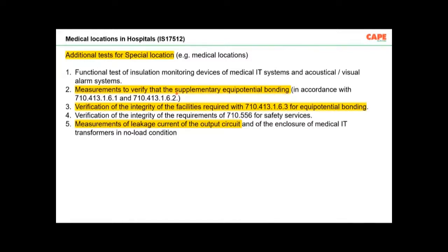Imagine you have an operation theater. All the metallic items in that particular operation theater must be interconnected in such a way that during normal condition, the touch voltage between two simultaneously accessible parts is less than a certain millivolt, maybe 30, 40 millivolt. So you need to have a very good connection.